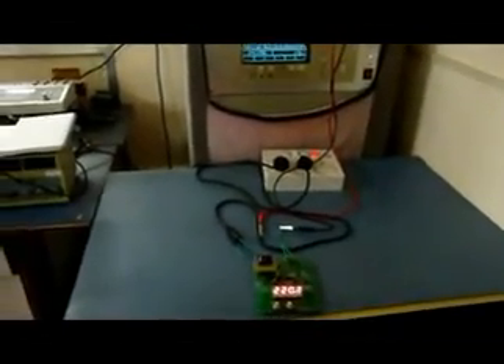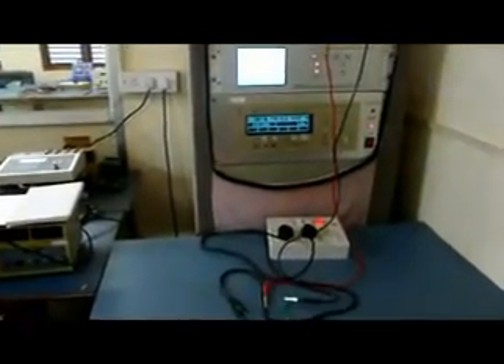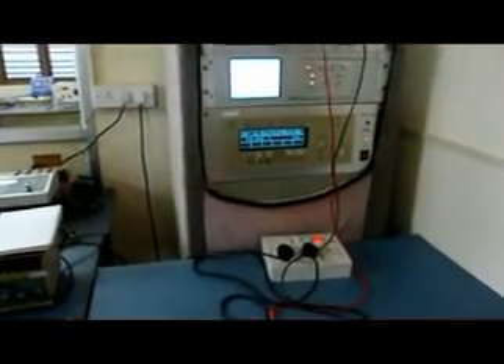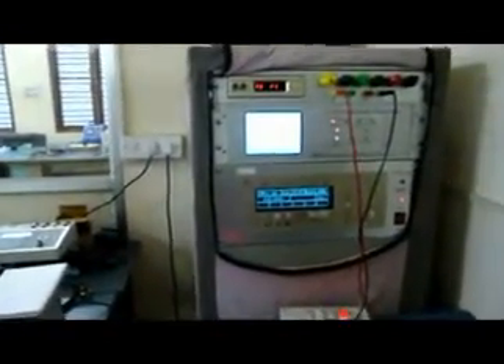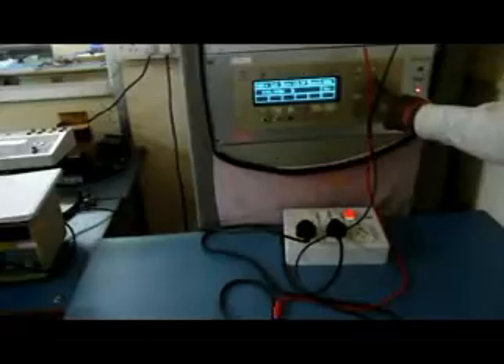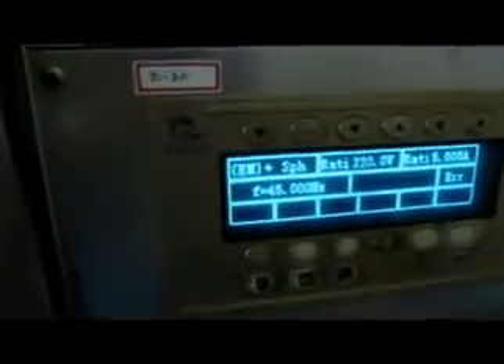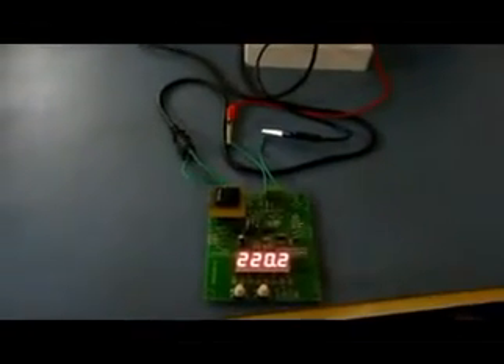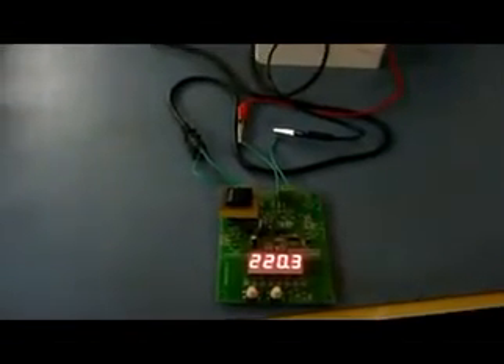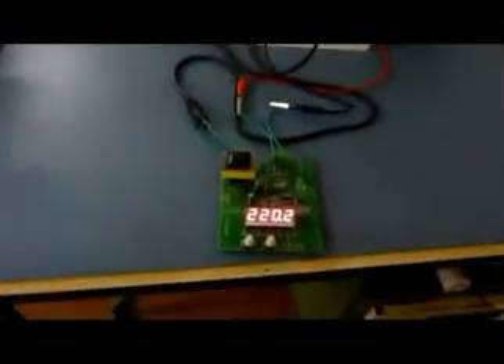Now we will keep the voltage constant at 220 volts, which is 100% of the source, and we will change the frequency in the range that we had specified, that is 45 to 63 Hz. So we can change the frequency to 45 Hz now. The frequency is now 45 Hz. You can see it here on the reference meter, and the reading on the panel meter is still 220.0. We'll now change it to 48 Hz. We'll wait for the frequency to settle. You can see 47 point, and the reading on the meter is still the same.